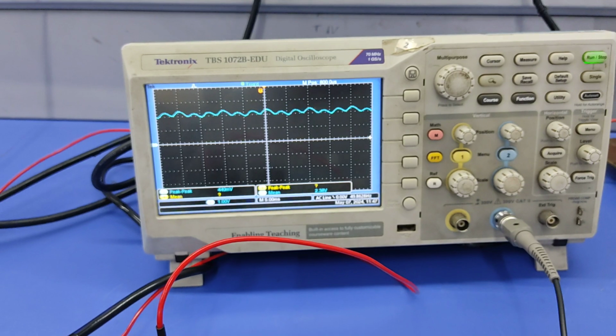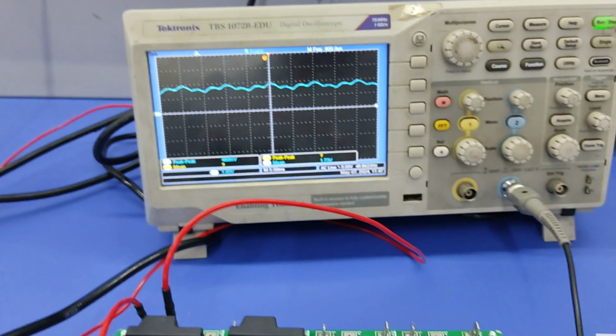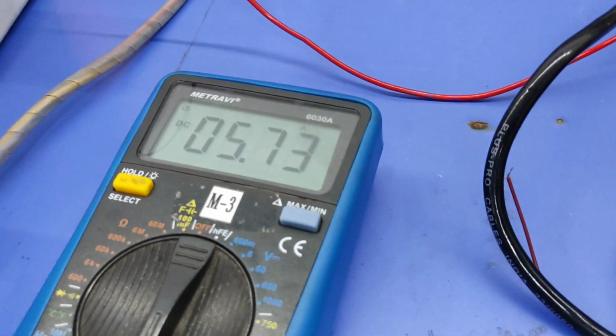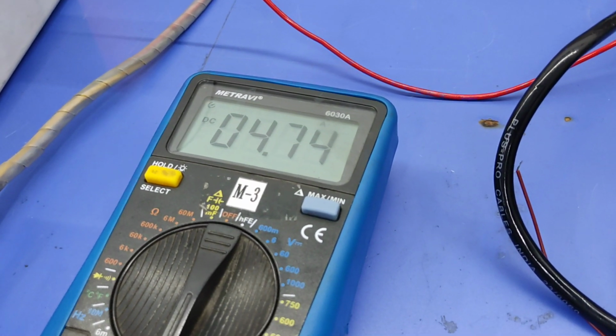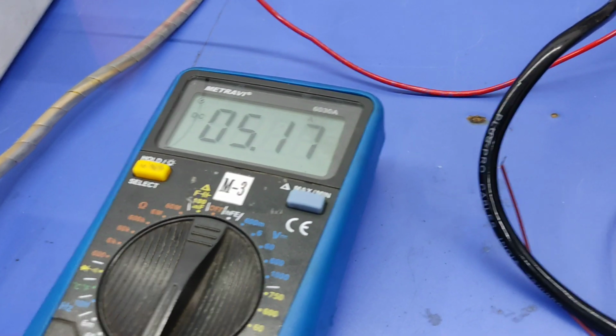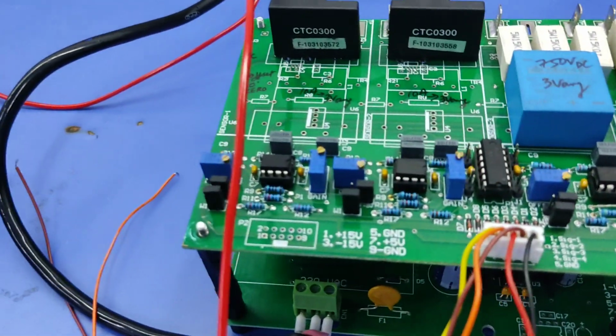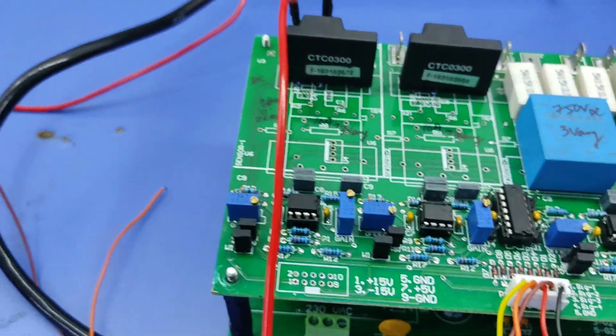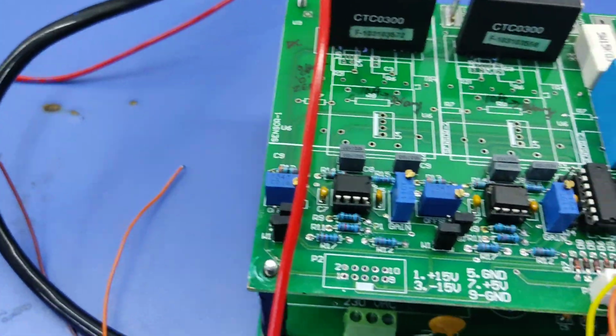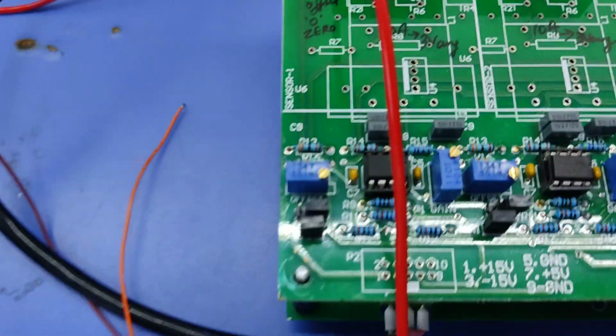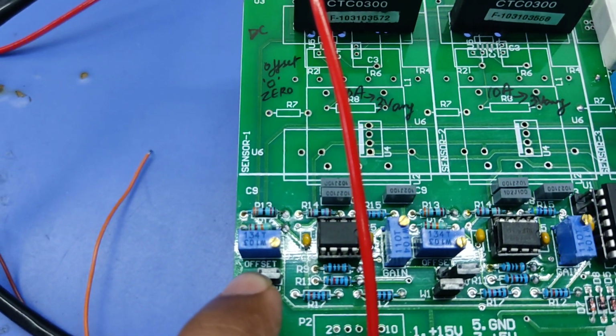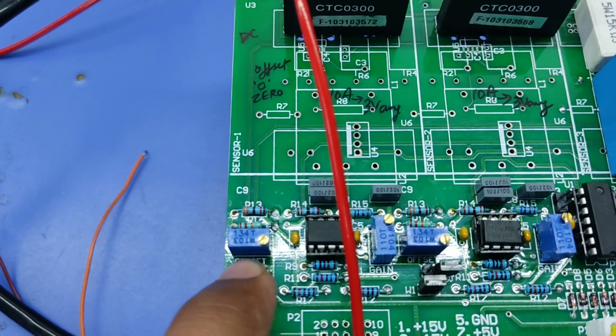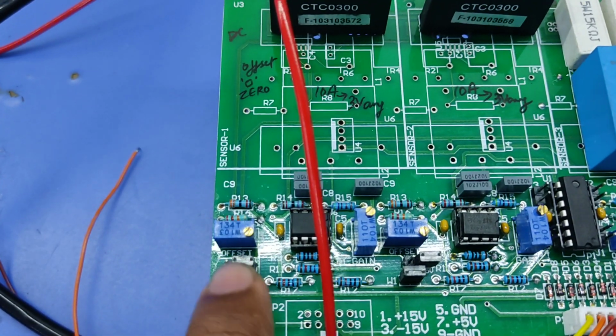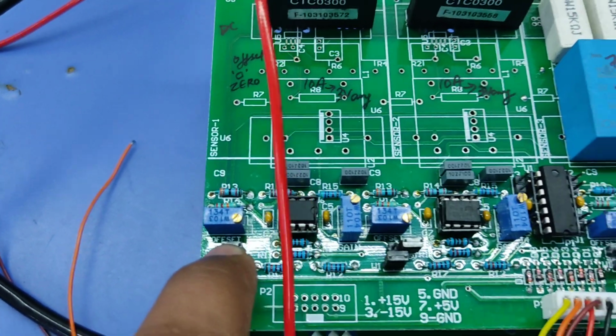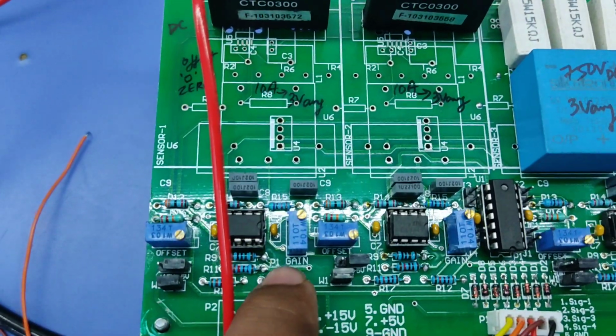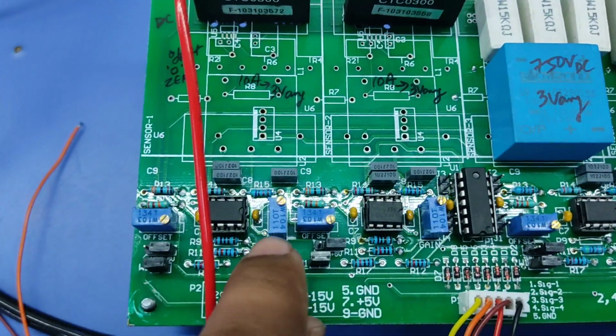Now we will see how to calibrate this. Our current is set to 5 ampere. If you want to set any offset or gain, you can use these two pots. First, the offset: for the DC current and voltage sensor, the offset value is 0. Then, if you want to change the gain value, you can use this pot.